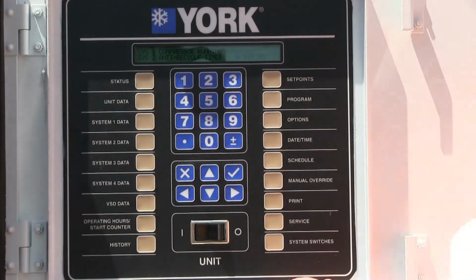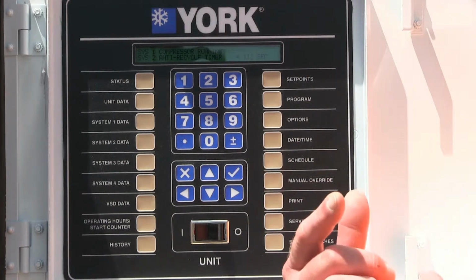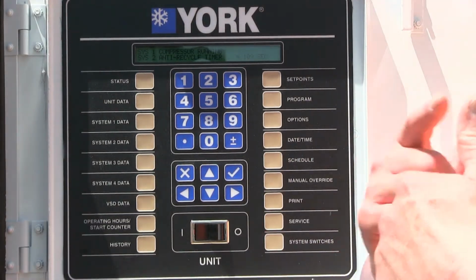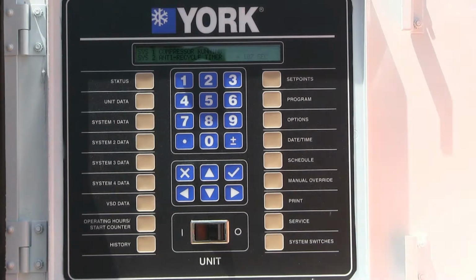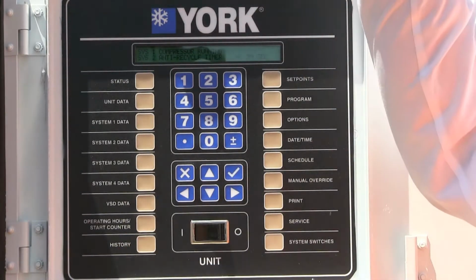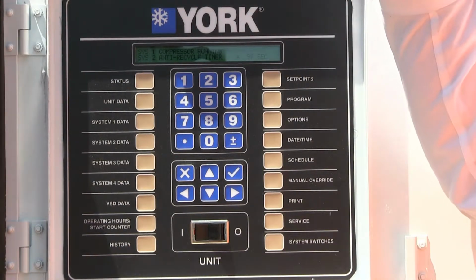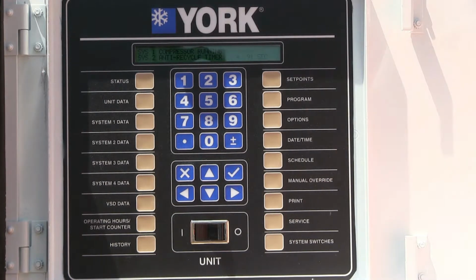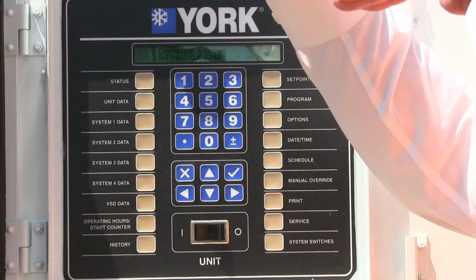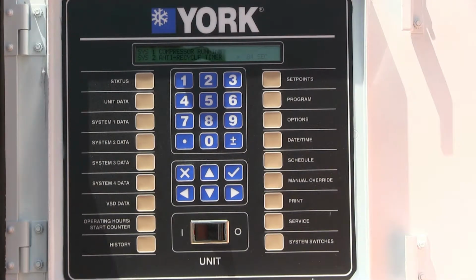We'll go back to our status. You can see compressor 1 is running, and again, this starts on a variable speed drive, so it starts out real slow, and it's going to just start ramping up faster and faster. The way the machine's going to work is it's going to try to catch the load with the first 100 tons and go from 0 to 100% capacity. When it feels like or calculates that it cannot maintain the load, it's going to slow that compressor down to about 10%, then start both compressors, and they'll work in unison, and they'll go up and load themselves up to full capacity. You can hear the machine starting to go up to wind up.